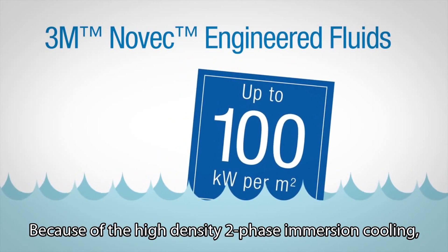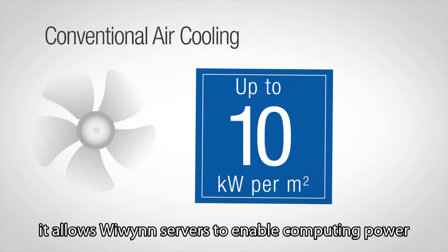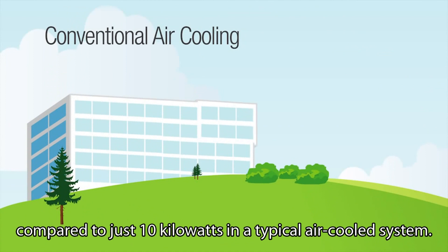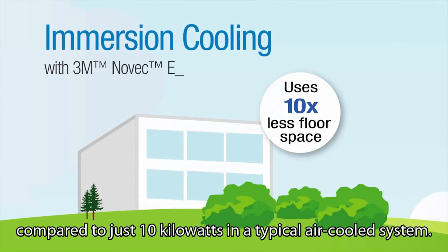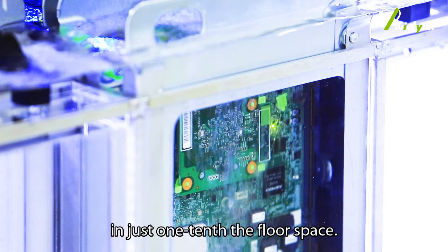Because of the high-density two-phase immersion cooling, it allows Wiwynn servers to enable computing power up to 100 kilowatts per square meter, compared to just 10 kilowatts in a typical air-cooled system. This means your facility can now be housed in just one-tenth the floor space.